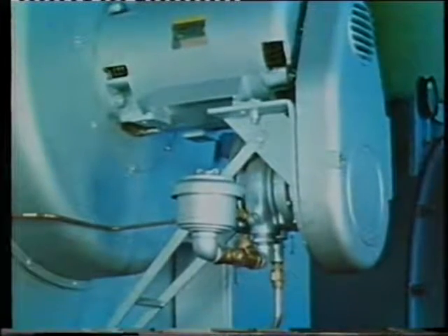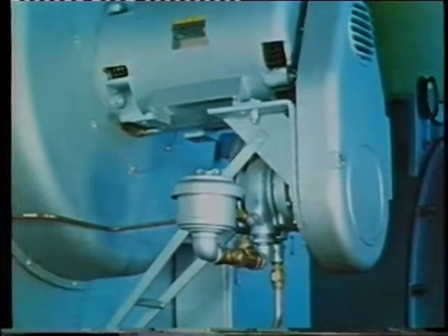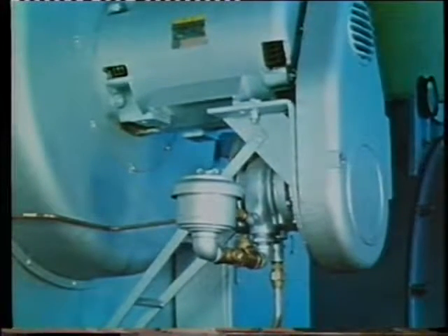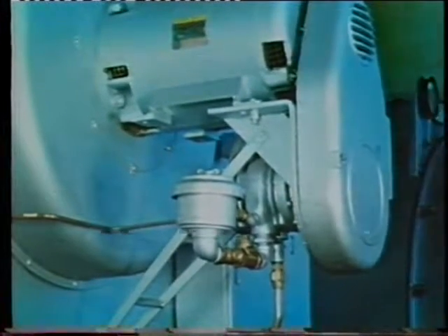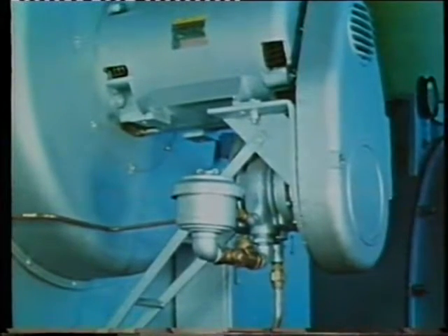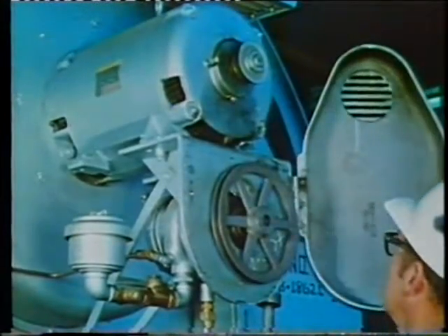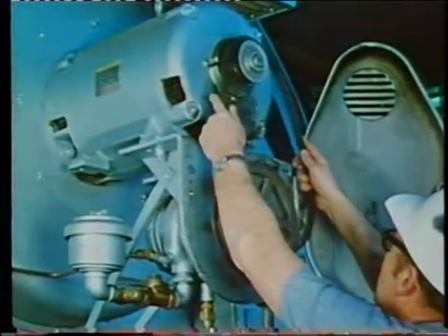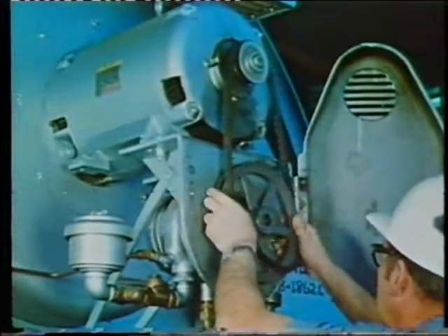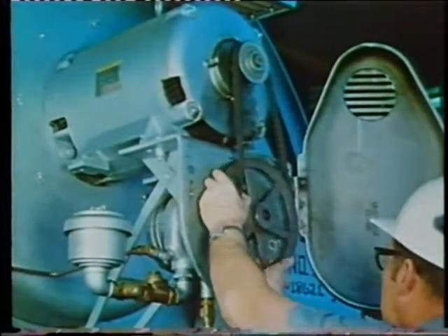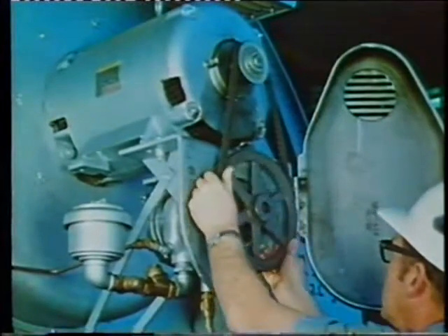For satisfactory combustion, the fuel oil must be atomized as it leaves the nozzle. Atomizing air, or primary air, is pumped to the burner nozzle where it mixes with the oil and provides the proper pattern in the combustion chamber. An atomizing air pump may be driven by the blower motor. Steam or compressed air may also be used on boilers to atomize oil for combustion.